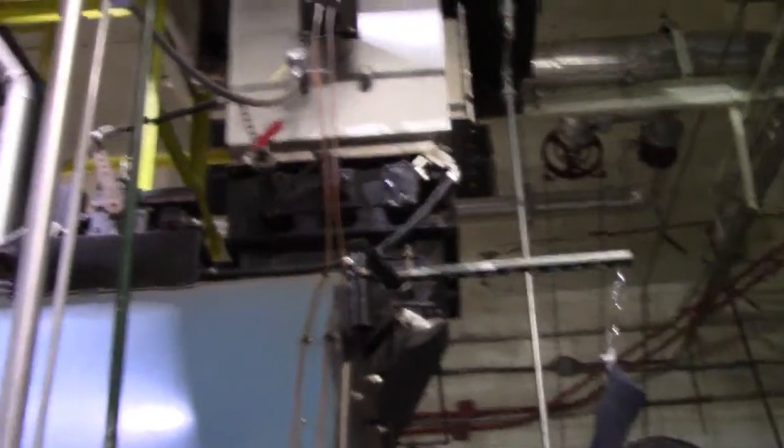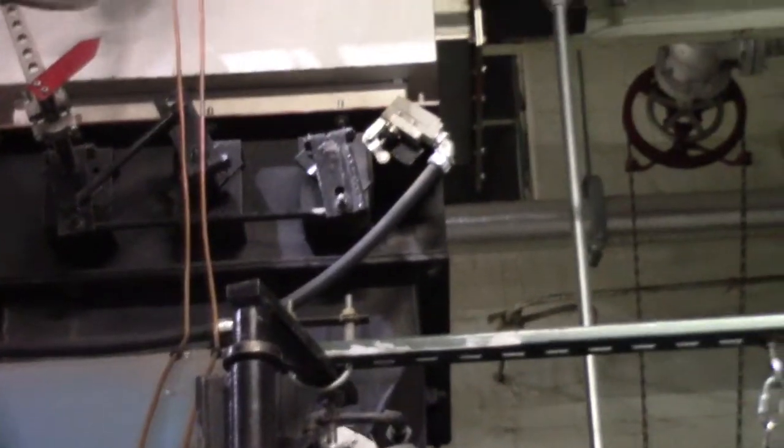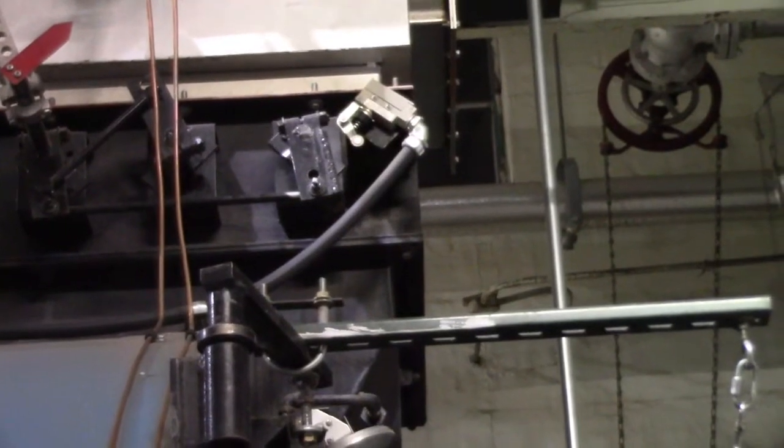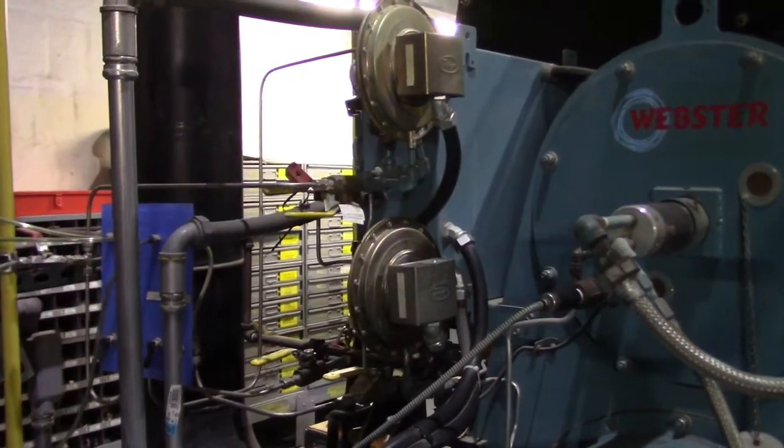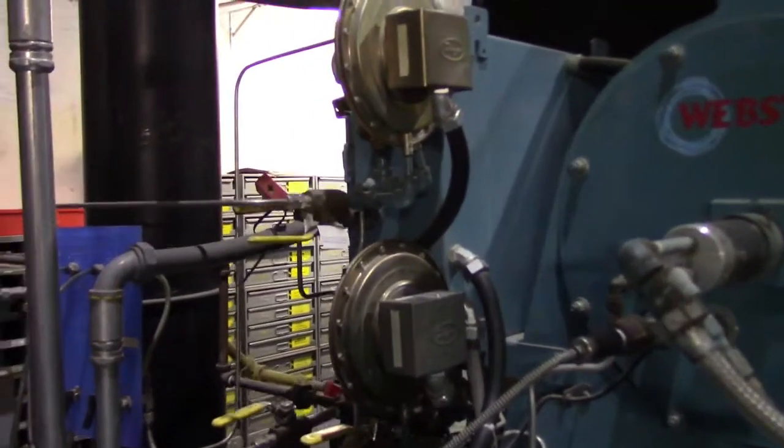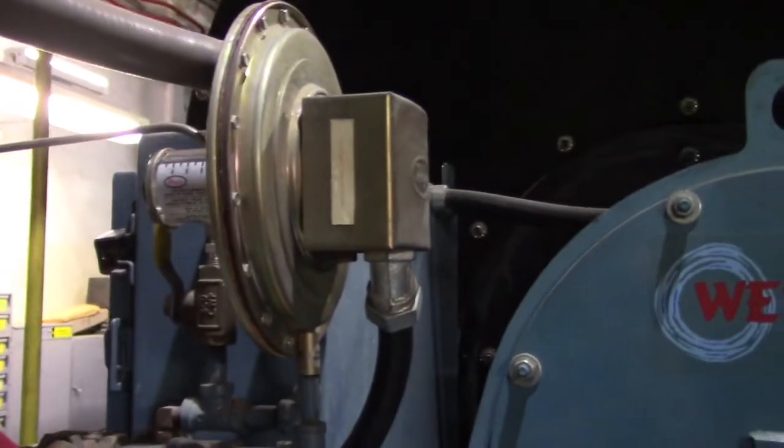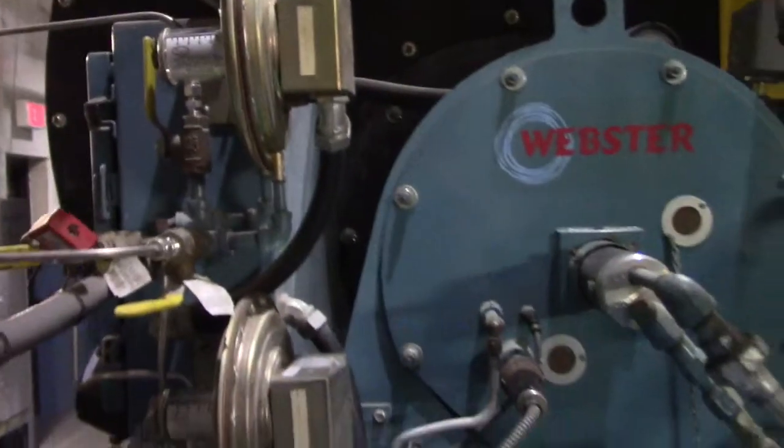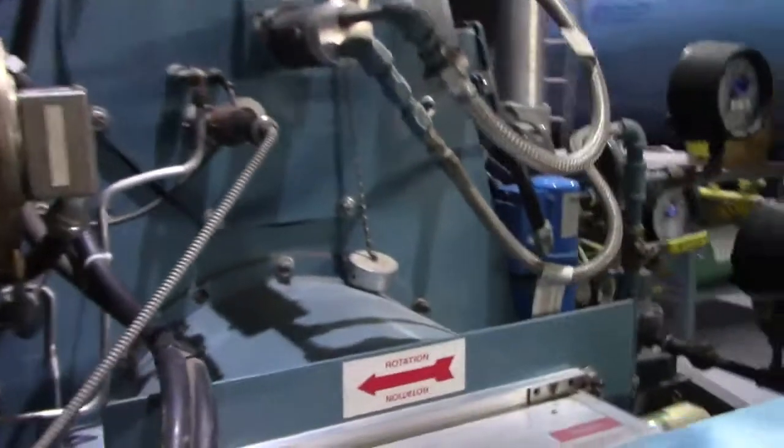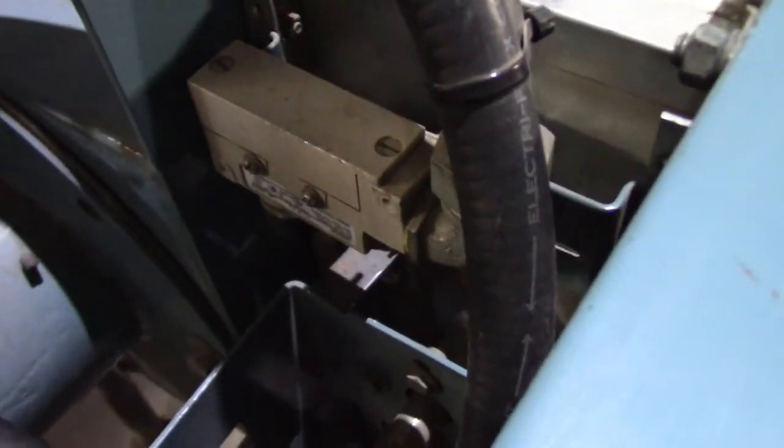One of the three components was the outlet stack damper, this switch. Another component was the purge air proving switch, this switch. And the third component was the inlet damper switch, or high fire switch, which is that switch.